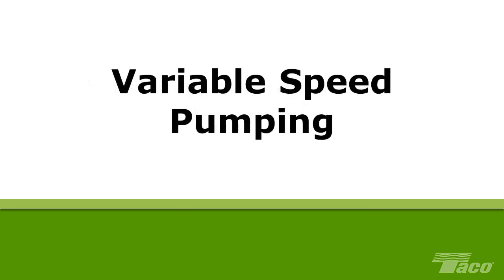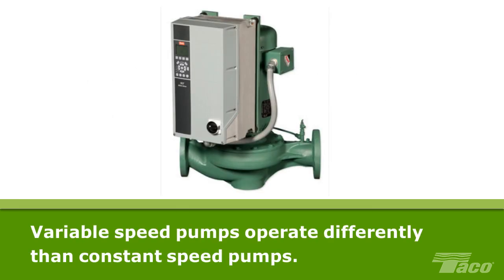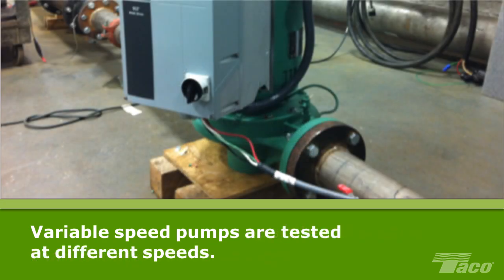Variable speed pumping. The way variable speed pumps operate is significantly different from how a constant speed pump operates. Manufacturers collect pump data in a similar way for variable speed pumps, but instead of testing at different impeller diameters, the pumps are tested at different speeds. There's only one impeller trim for each motor horsepower per model.